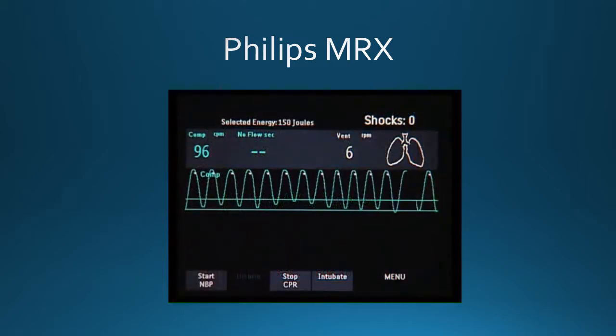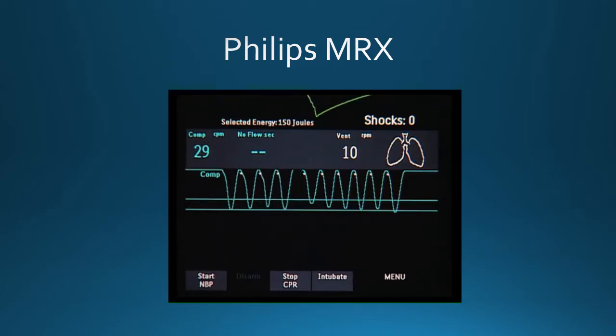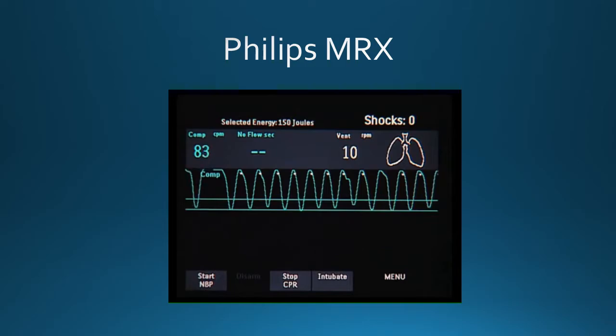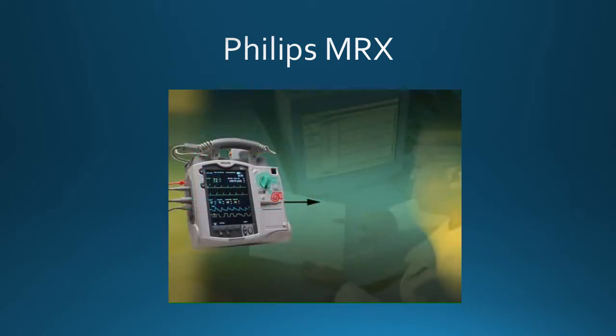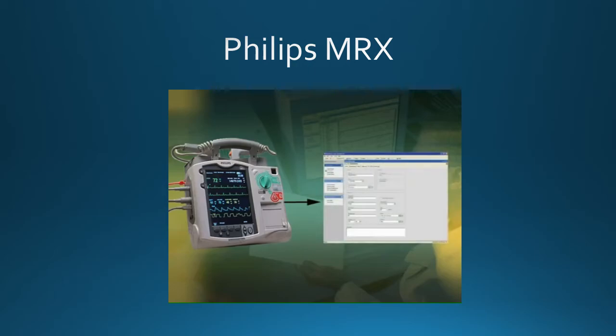The QCPR option provides real-time corrective feedback on the rate, depth, and duration of compressions, as well as when pressure is not released between compressions. It also provides the rate and approximate volume of ventilations and notification of lack of CPR activity. The MRX then automatically stores critical event data from all 4 modes for later download to Philips' data management solution, HeartStart Event Review Pro.